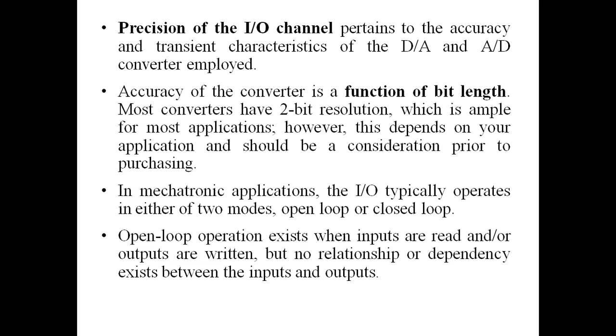A manufacturer of compressors may use the open loop method for automatic compressor testing. A time-based sequence is often employed. At time t1, a signal is sent to the compressor motor, which resets the motor speed to the specified value. After waiting a pre-selected time of T seconds for the equipment to hopefully stabilize, the pressure, temperature, flow and speed are read and saved in memory.